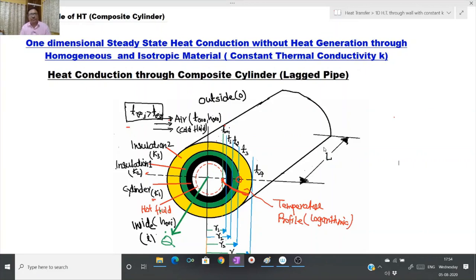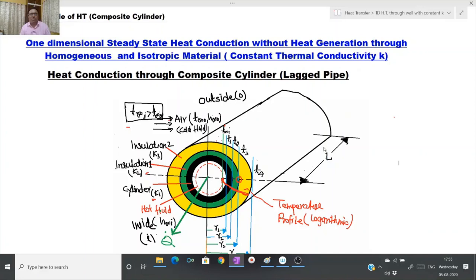What is a composite cylinder? An example is a steam pipe carrying high-pressure steam from a boiler to a turbine. It is provided with two or three layers of insulating materials of different thermal conductivity, and finally a material like plaster is provided over these to make it stronger. The purpose is to prevent heat loss from the steam to the surroundings. Such a pipe is called a composite pipe, sometimes also referred to as a lagged pipe. The process of providing different layers of materials over a base cylinder is called lagging.